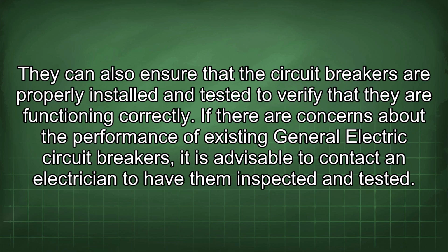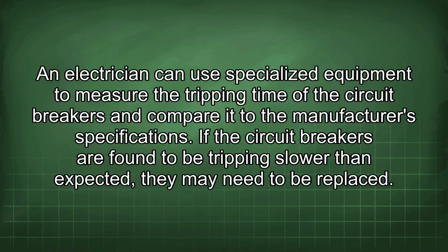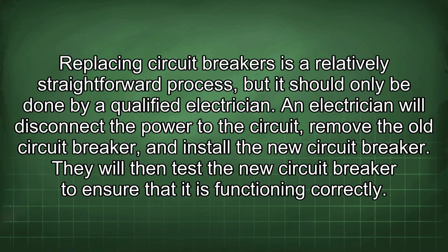They can also ensure that the circuit breakers are properly installed and tested to verify that they are functioning correctly. If there are concerns about the performance of existing General Electric circuit breakers, it is advisable to contact an electrician to have them inspected and tested. An electrician can use specialized equipment to measure the tripping time of the circuit breakers and compare it to the manufacturer's specifications. If the circuit breakers are found to be tripping slower than expected, they may need to be replaced.